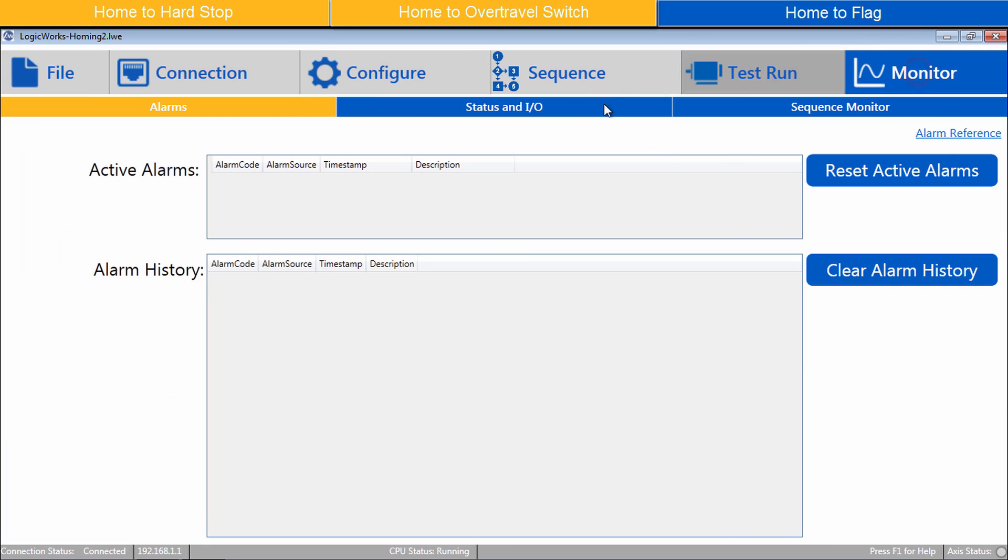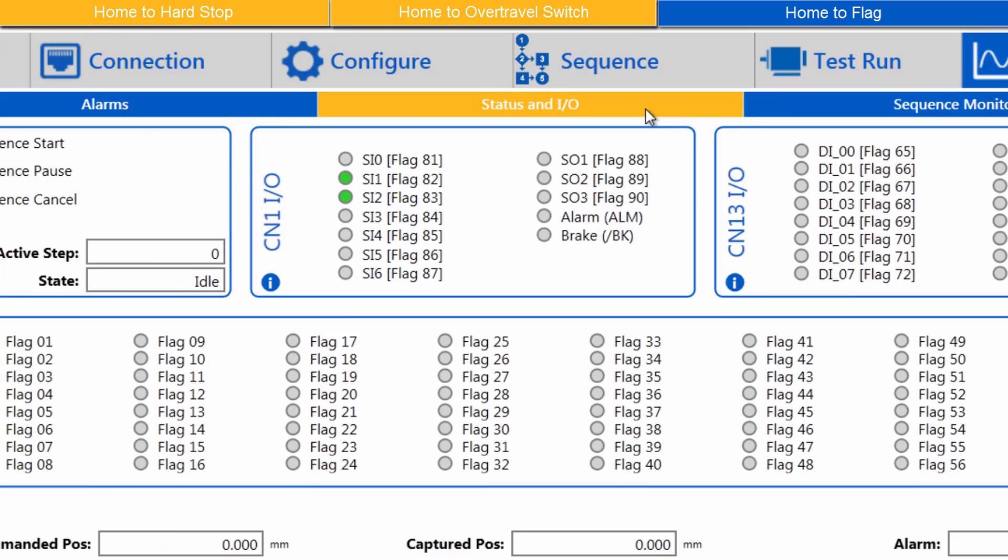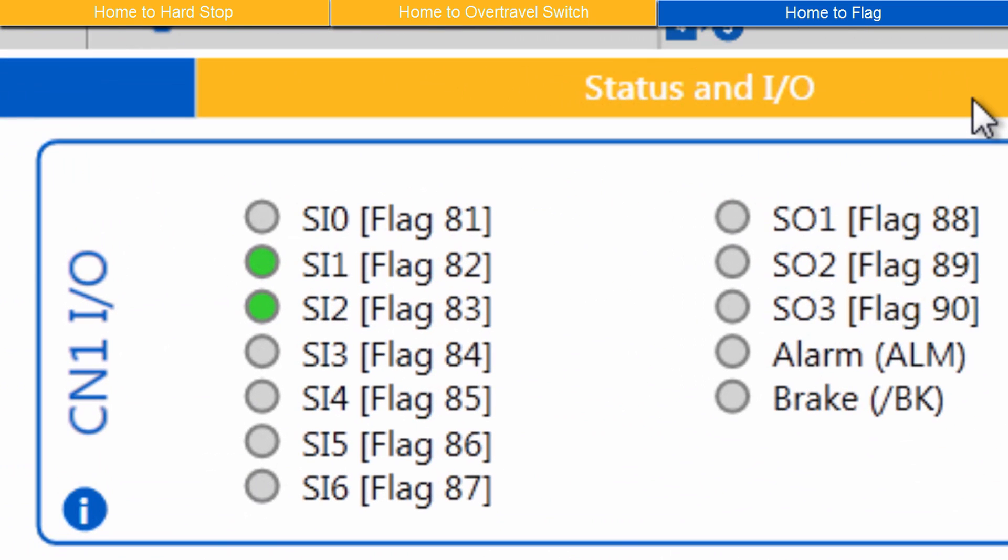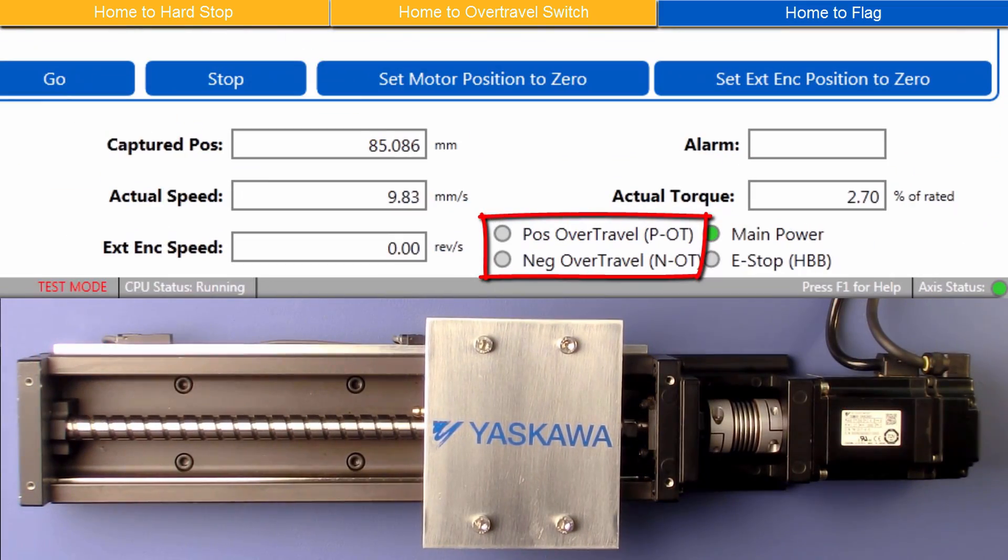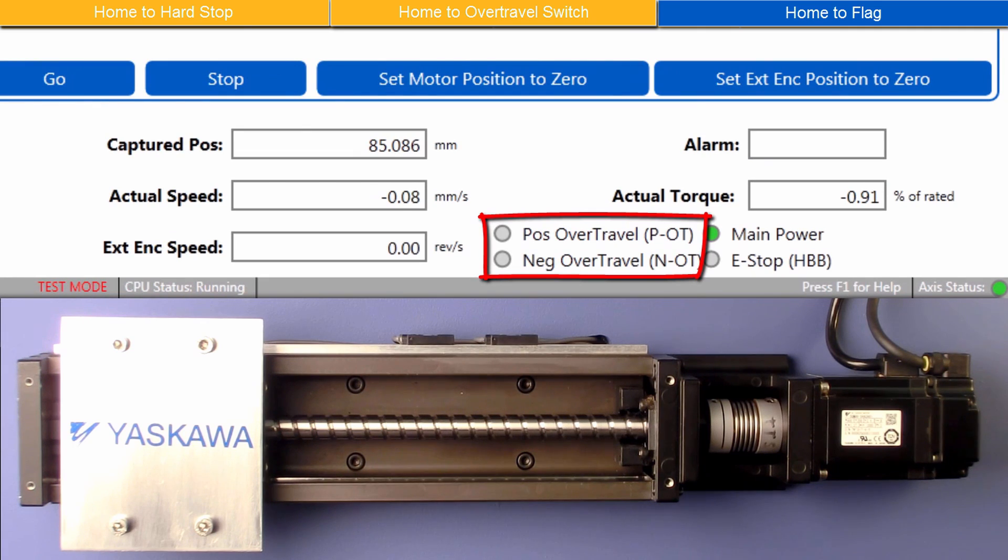Monitor, Status and IO gives additional wiring and status information. The Over Travels are wired to inputs SI1 and SI2, Flag 82 and 83. And I have previously tested that the Over Travels really do stop motion.